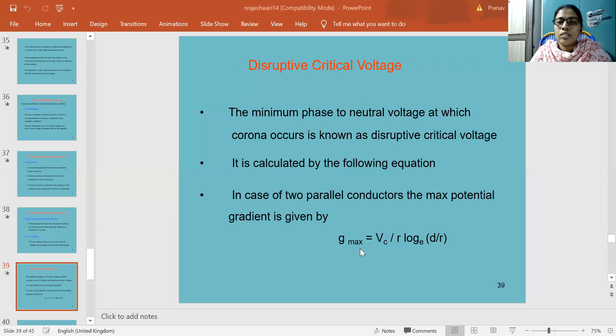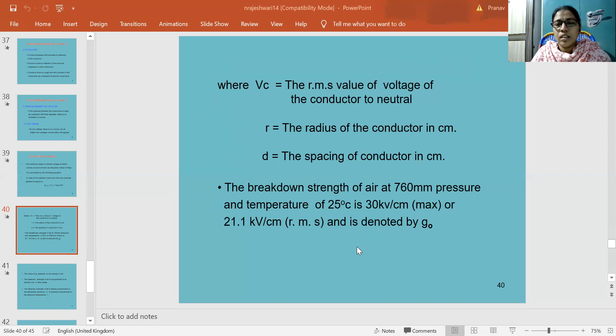So in the case of two parallel conductors, the maximum potential gradient is given by g maximum, which is equal to Vc by r into log of d by r. Where Vc is the RMS voltage of the conductor to neutral, small r is the radius of the conductor in centimeters, and d is the spacing between the conductors in centimeters. The breakdown strength of air at 760 mm pressure and temperature of 25 degrees centigrade is 30 kV per centimeter maximum, or 21.1 kV per centimeter RMS, and is denoted by g naught.